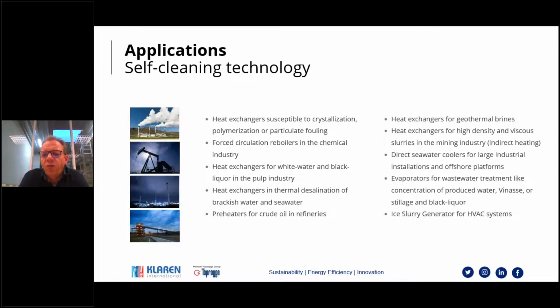Another area of concern is evaporators for almost all types of wastewaters that contain salts, but also sometimes contain organics. Here the fluidized bed technology has shown that we can concentrate, avoiding fouling and even going to higher concentrations. The last application to mention is ice slurry generators. Maybe not ice slurry generators in total, but more every time that the heat exchanger would face fouling by the formation of an ice layer, the same phenomenon as fouling, also an insulating layer. The particles are also able to remove this ice layer from a wall.